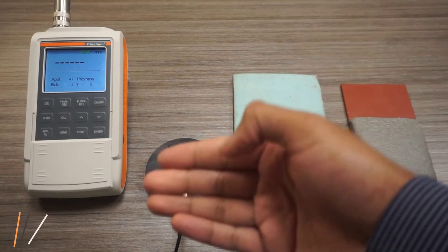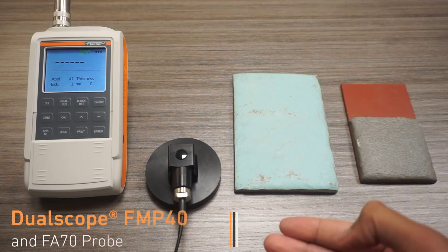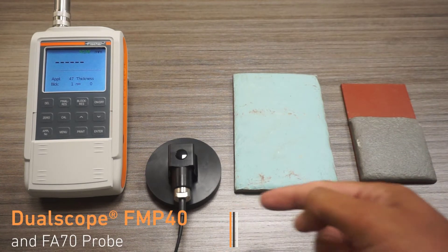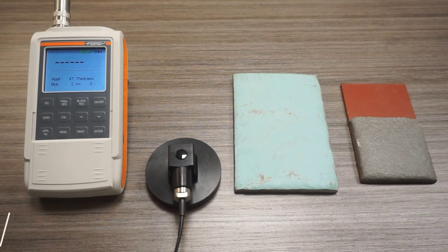I have a Dualscope FMP40 with an FA70 probe to demonstrate its measurement capabilities on applied intumescent coatings over structural steel. The FA70 probe ships with these two certified standards and a base plate. The thinner standard is 18.2 mils and the thicker one is 799 mils, so it covers a wide range of coating thicknesses.